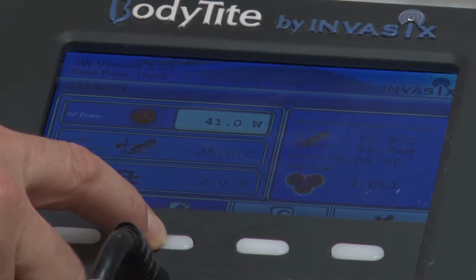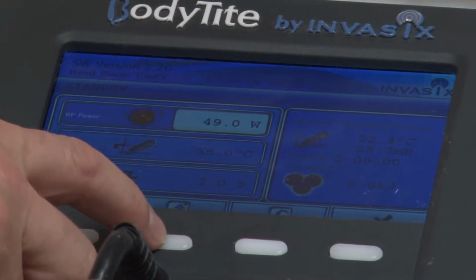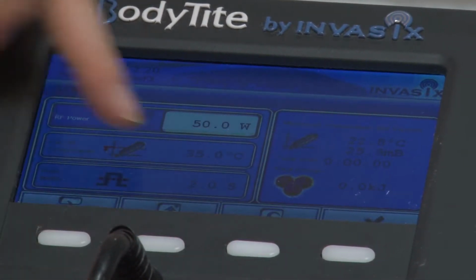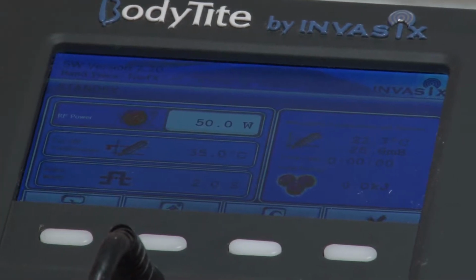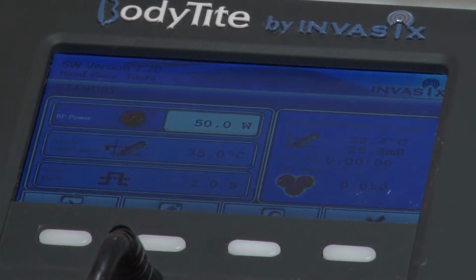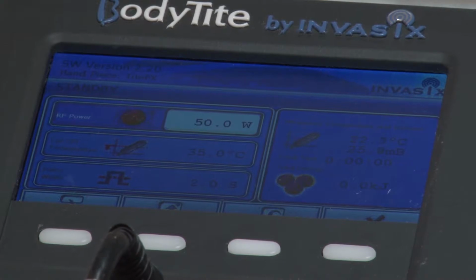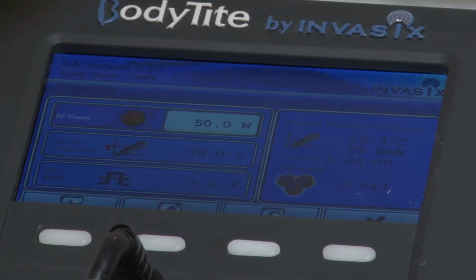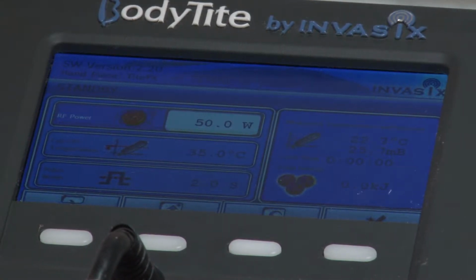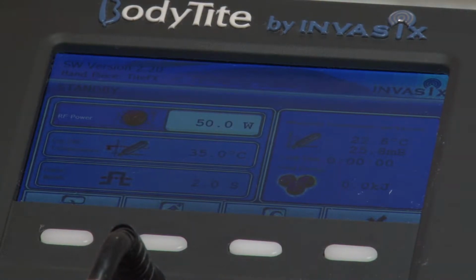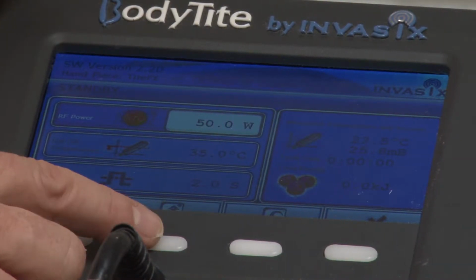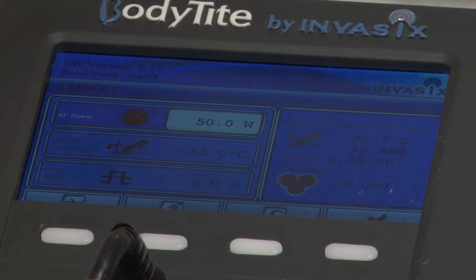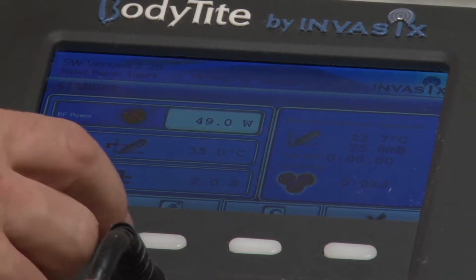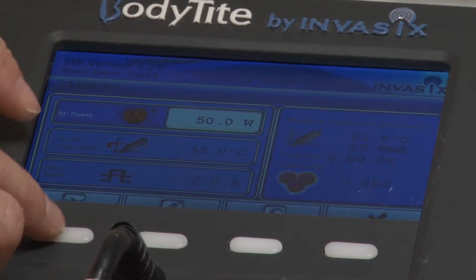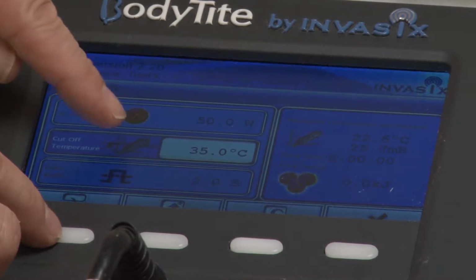Once you get to 50 watts of energy, you can control the endpoint, the thermal endpoint. This is a thermally modulated RF delivery system, like an air conditioner. It turns the RF on and off because it's monitoring epidermal temperature and impedance at all times. In general, to get therapeutic tissue tightening, you want to heat that skin up. We use our menu to get down to temperature. We want to get an endpoint.